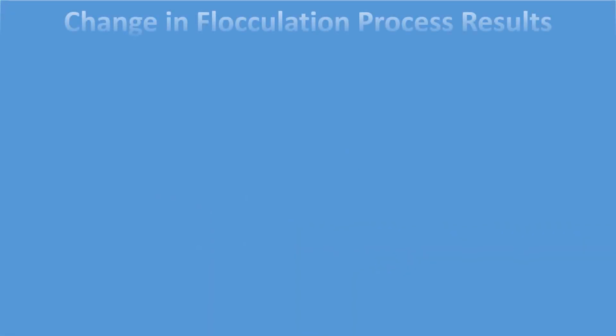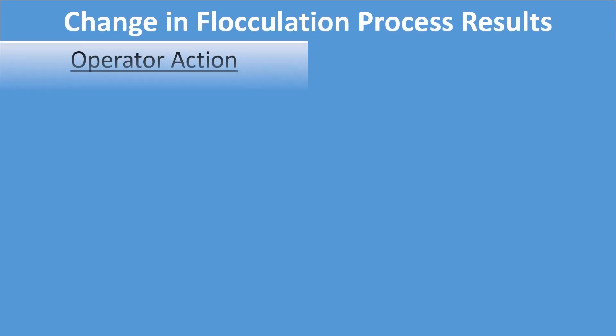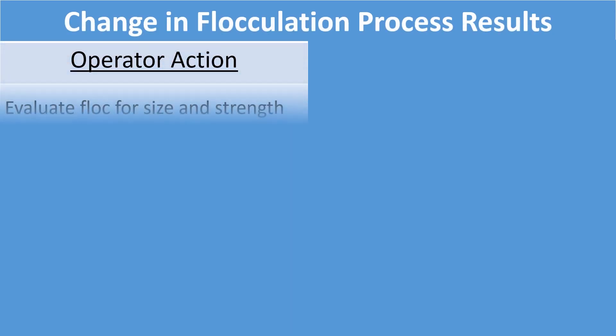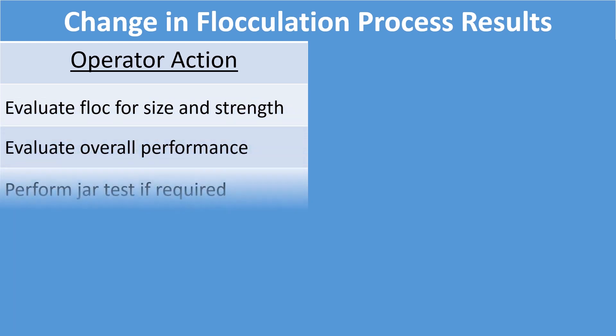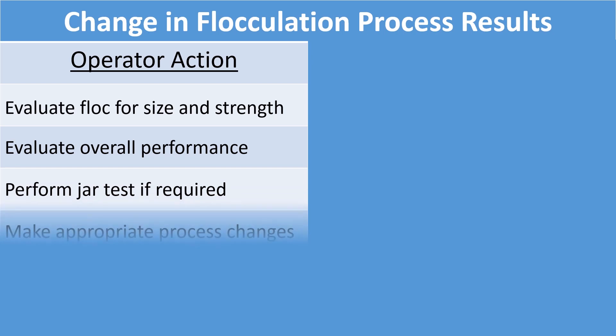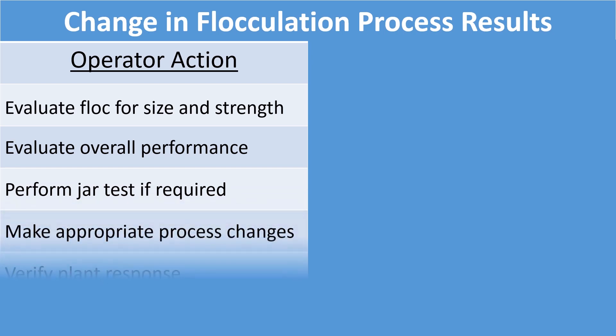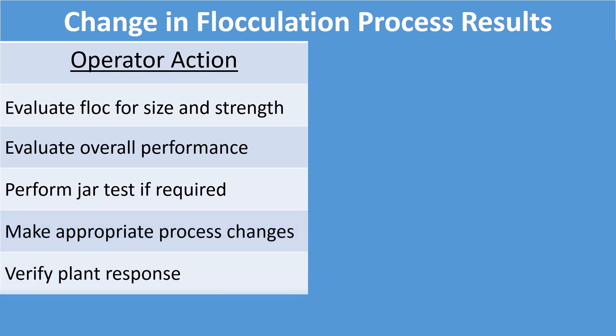Regarding operator actions if there is a change in flocculation process results: the operator needs to evaluate the floc for its size and strength, and this is primarily a visual inspection. Is the floc tight and large, or is it pin floc? Pin floc is not good for settling — you want large, tight floc. The operator should evaluate overall performance, perform a jar test if required, make appropriate changes, and then verify that the plant responded as expected.